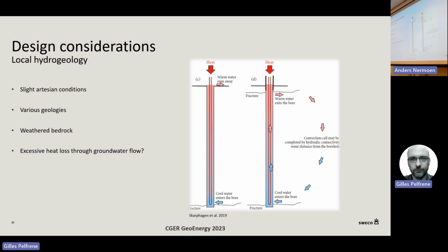One potential driver for losses is groundwater flow, which can move from a high pressure area to a lower pressure area, for example from north to south. In this case that's not present, based on the thermal response test we did.